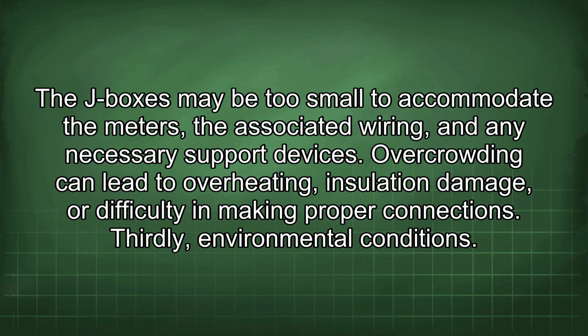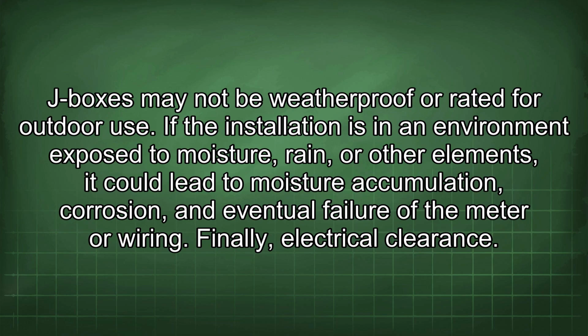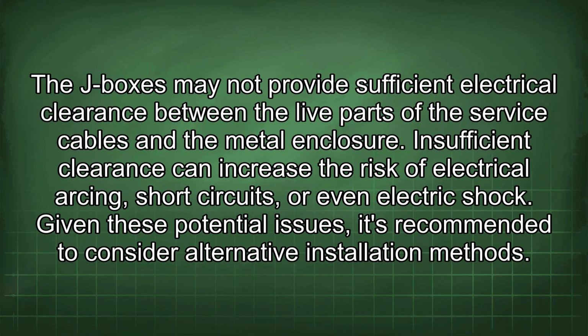Thirdly, environmental conditions. J-boxes may not be weatherproof or rated for outdoor use. If the installation is in an environment exposed to moisture, rain, or other elements, it could lead to moisture accumulation, corrosion, and eventual failure of the meter or wiring. Finally, electrical clearance. The J-boxes may not provide sufficient electrical clearance between the live parts of the service cables and the metal enclosure. Insufficient clearance can increase the risk of electrical arcing, short circuits, or even electric shock.